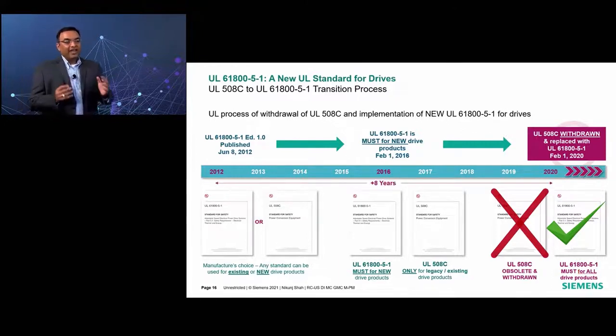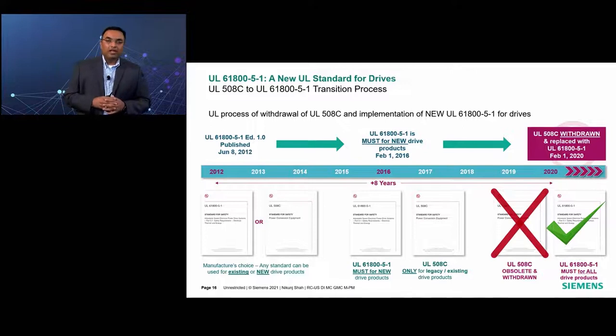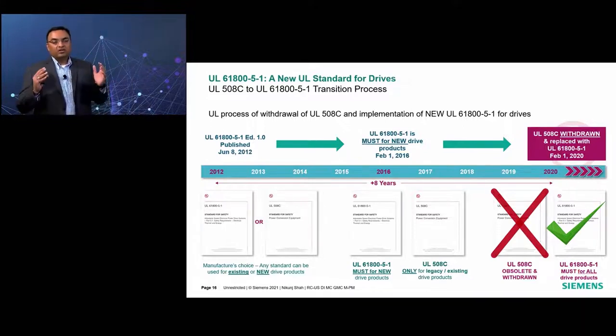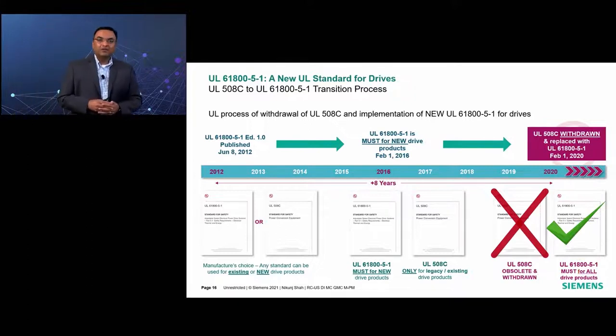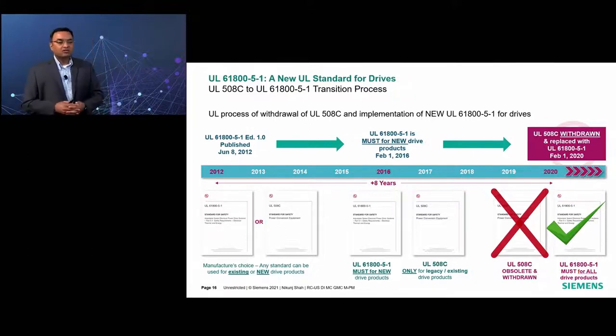There are about 8 years of total timeline that is more than adequate, which was given by UL to all the drive manufacturers to switch over their products from UL 508C to UL 61800-5-1. And this timeline was also given to the equipment manufacturers, OEMs, system integrators, panel builders, etc., who are using this drive in their equipment as a component.